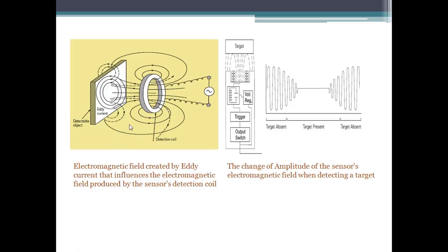the electromagnetic field emitted from the sensor produces eddy currents circulating around the target surface. This eddy current generates its own electromagnetic field that influences the oscillator field of the sensor. It decreases the amplitude of the electromagnetic field produced by the sensor.